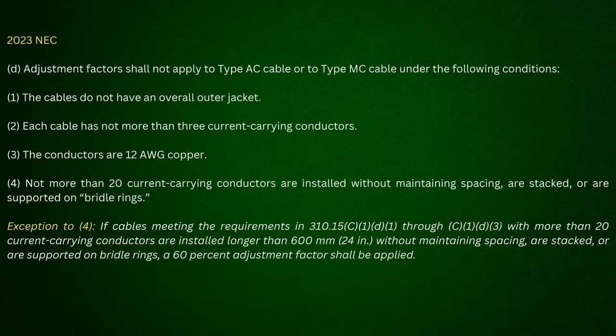And right here it says, adjustment factors shall not apply to type AC or to type MC cable in the following conditions. Let's see what it says. The cables do not have an overall outer jacket. Each cable has not more than 3 current carrying conductors. The conductors are number 12 copper, and not more than 20 current carrying conductors are installed without maintaining spacing or stacked or supported on bridle rings. Same type of language we saw before. So basically, you're looking at these AC cables, but they're being installed from point to point. You see what I'm saying? They're not inside another raceway or something.